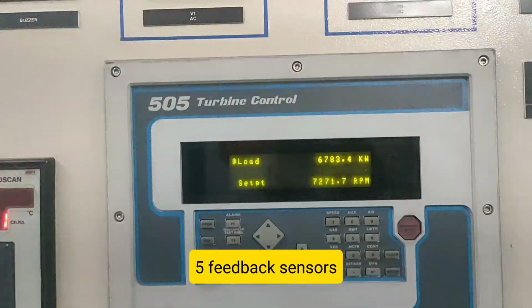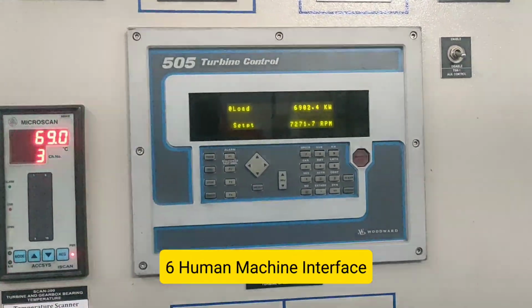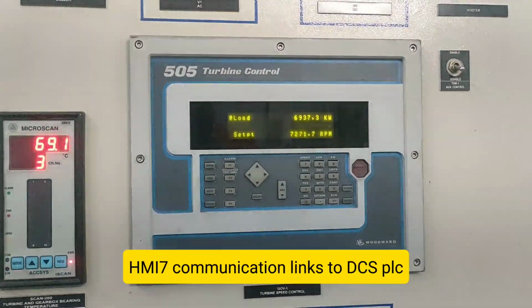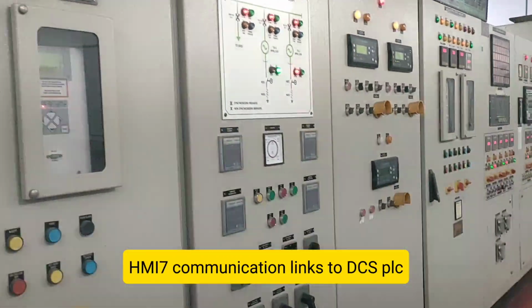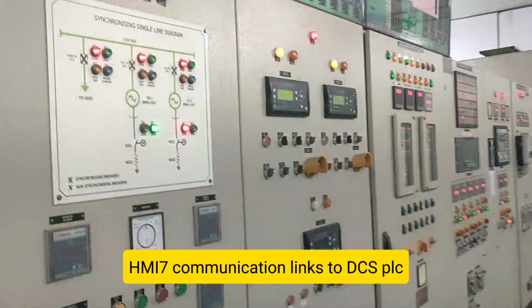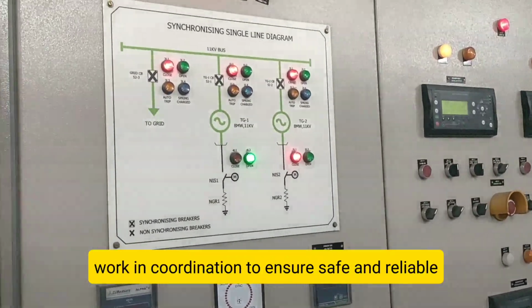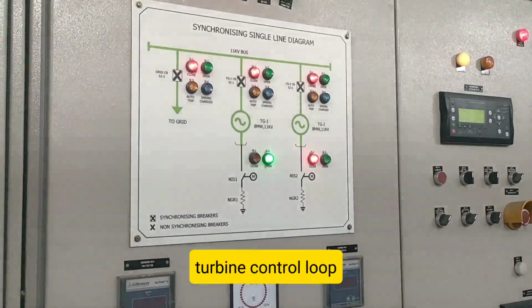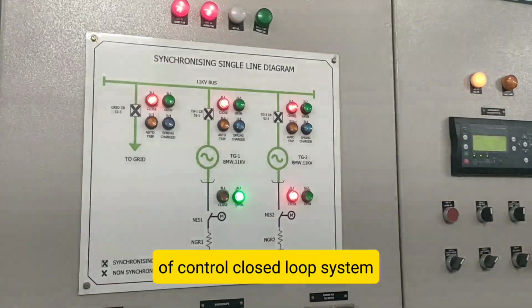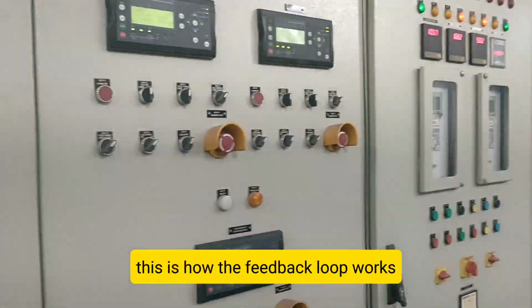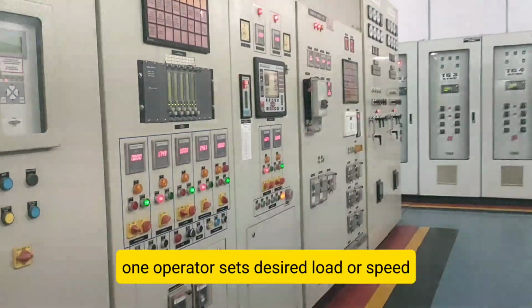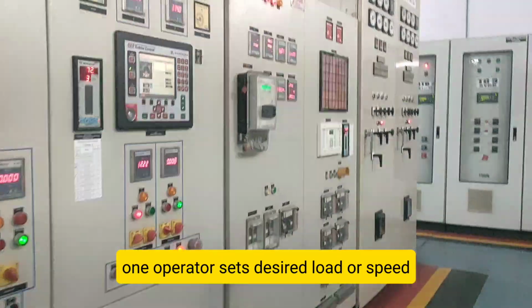Testing the Governor system. Before startup, several tests are performed. Governor response test: check how fast the actuator responds. Valve travel test: ensure throttle valves move across full range. Setpoint matching: test if the governor holds the set RPM and load under varying conditions. Simulated load drop test. These tests ensure the governor will perform safely and reliably during operation.